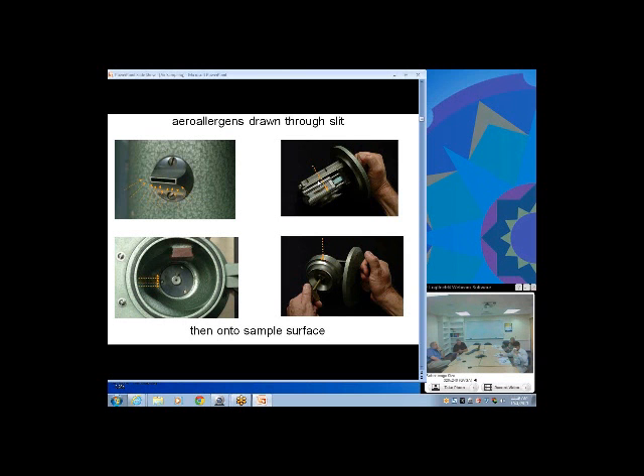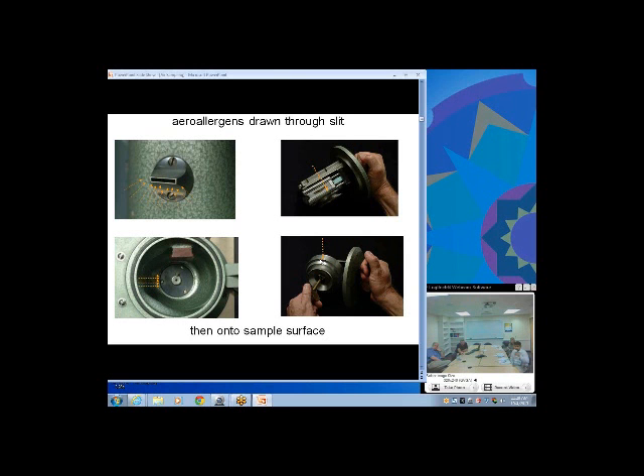When you get particles smaller than five microns — especially into the two micron range — efficiency can fall to as low as 50%. Some small ascus spores and aspergillus and penicillium spores are less than two microns. We normally don't calculate back for efficiency, but it is something you have to worry about. The Burkard collector is one of the best for efficiency for really small particles.